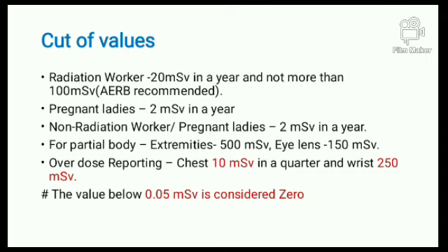Okay, next thing is, cut off the values of TLD batches. एक रेडिएशन वर्कर के लिए मैक्सिमम डोज लिमिट क्या होना चाहिए, 20 मिलीसीवर्ट पर ईयर, बट नॉट मोर देन 100 मिलीसीवर्ट. दैट इज अ रिकमेंडेशन बाय एआरबी.